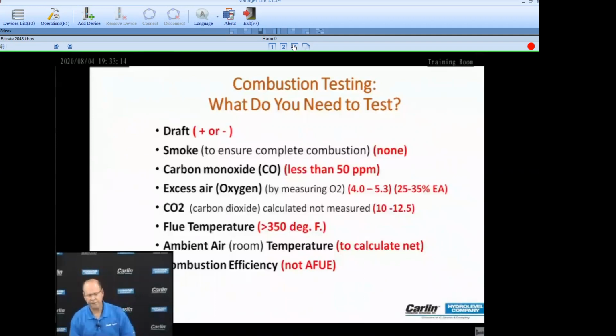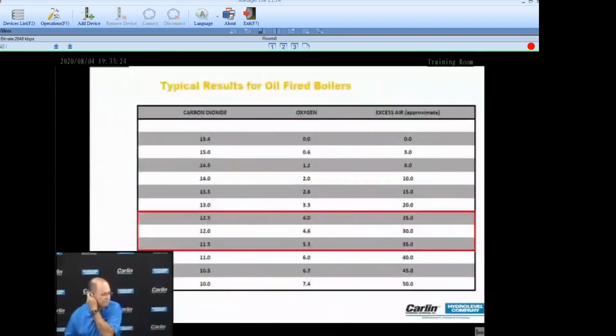And again, combustion efficiency, a result of stack temperature and CO2. That's the chart that we basically use. This chart here identifies a sweet spot for most techs, looking at 11.5% carbon dioxide to 12.5%. And here you can see the comparison to the O2 level, the oxygen, and how it relates in percentage to excess air. So the more excess air you add, the lower your CO2 is going to be, and the lower CO2 is going to reflect in your combustion efficiency in your end results.